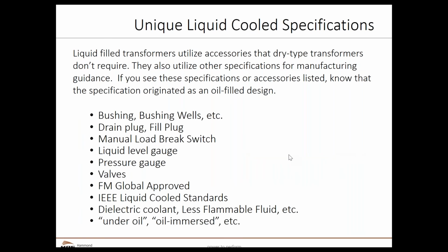So when we look at a specification for liquid filled, sometimes the transformer specification doesn't actually say liquid filled, or sometimes it does, but you have to kind of get into it. There are some clues though that will key us into liquid filled. When we hear the words bushing wells, anything that says bushing, anything that says drain plug or fill plug, again, these are typically associated with liquid filled units. That will tell us it's a liquid filled transformer specification.